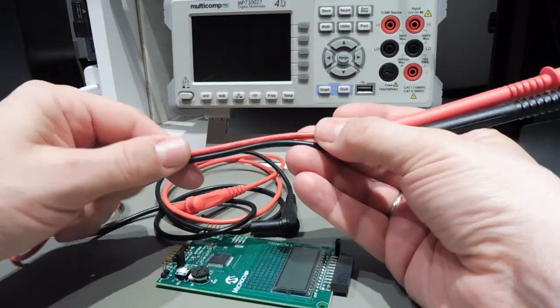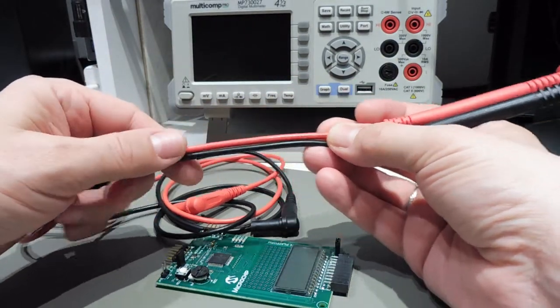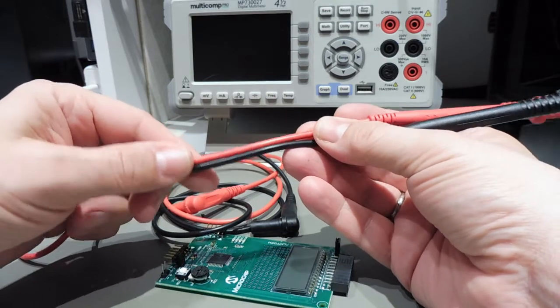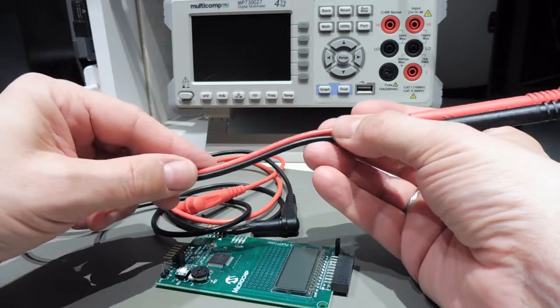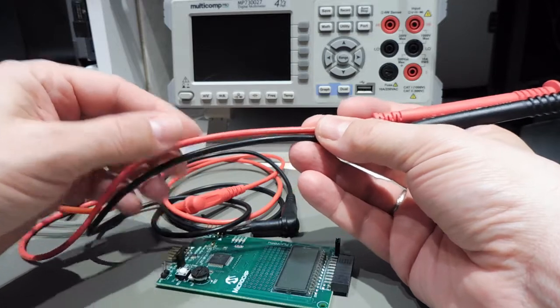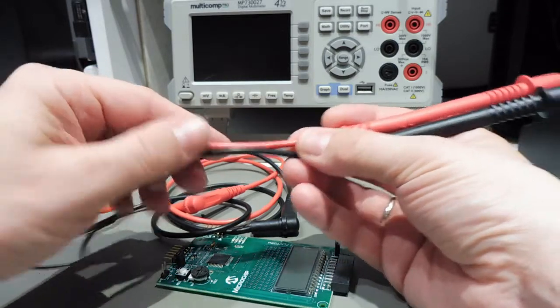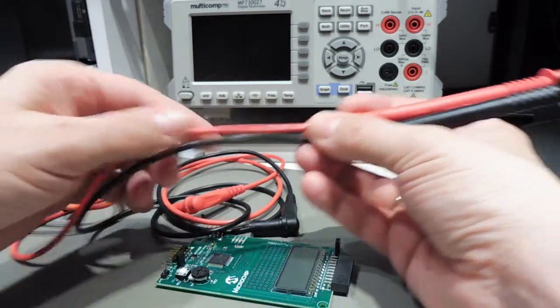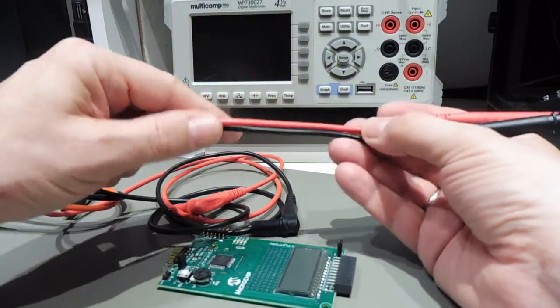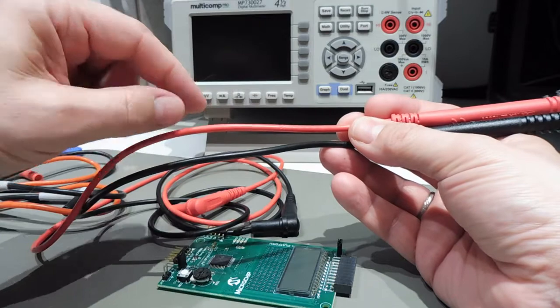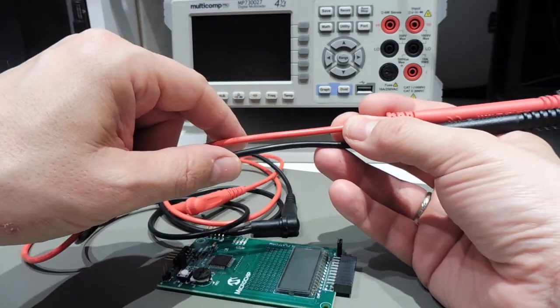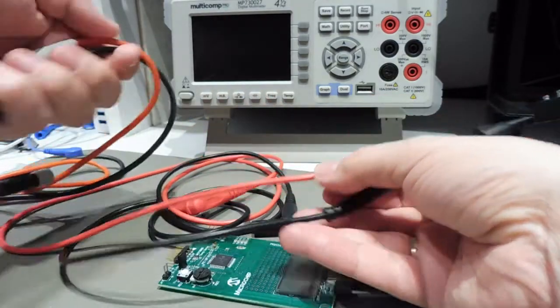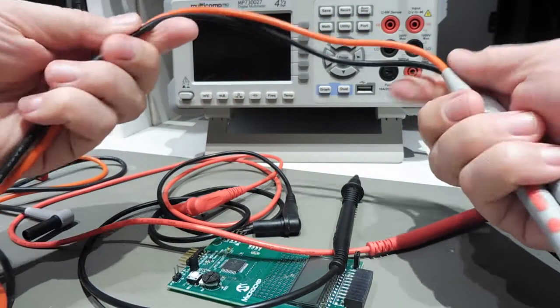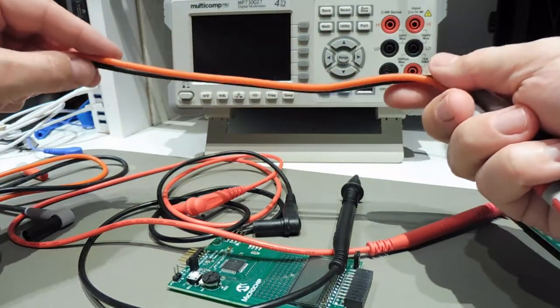Second, you look at the quality of the cables themselves. They should have silicone insulation, which is much more temperature resistant and softer than PVC. These probes here are PVC, which is quite soft and nice, but PVC is rated for about 100 degrees Celsius, whereas these cables here are rated for 150 degrees.